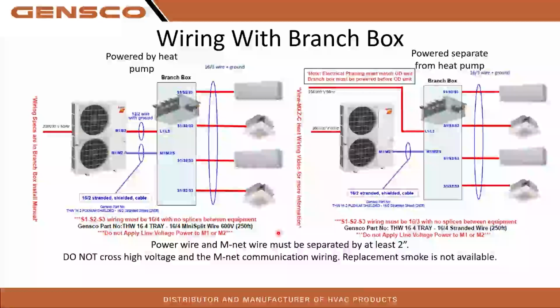Matthew said, what if wire is shielded? So you do want the shielded wire for M1, M2. On that 16/2 stranded shielded, there is a shield wire that comes in there. That shield will land on your S terminals. If you pay attention to those terminals, you'll notice that it's only grounded to the chassis of the heat pump. It's not grounded on the branch box. We do not want that shield wire grounded on both ends. We only want it grounded at the heat pump. What ends up happening is if you ground that thing to both ends or all of your equipment, it no longer is a shield, it is now an antenna, and it will pick up all interference. So you definitely don't want to do that.